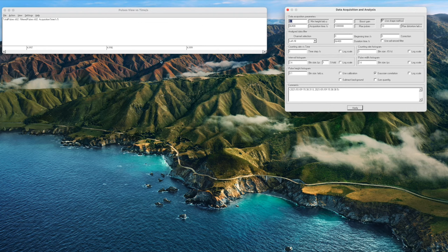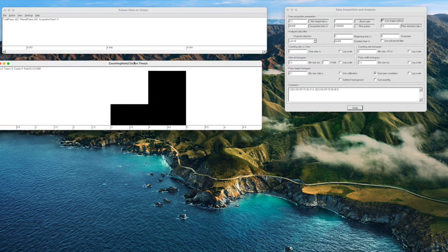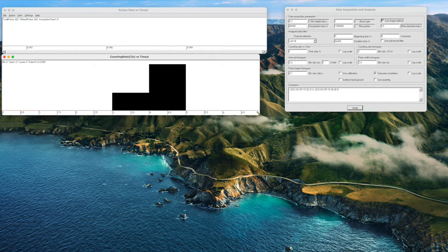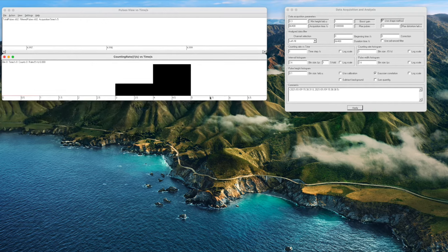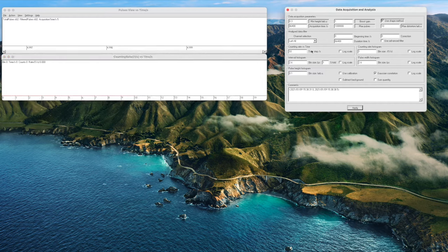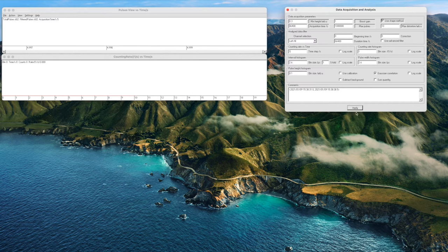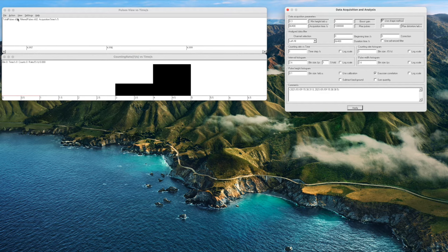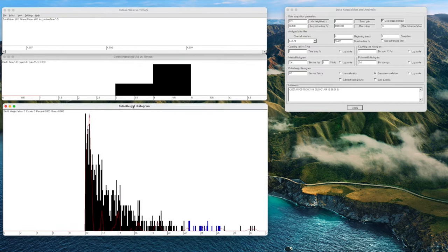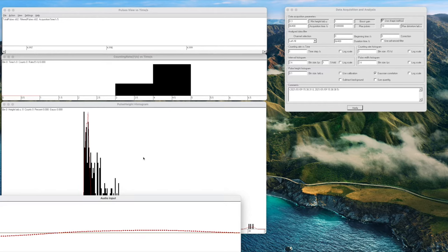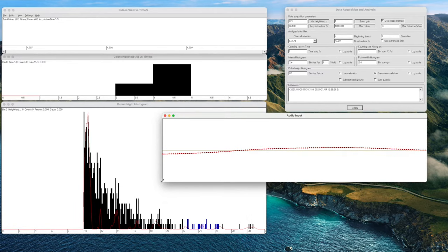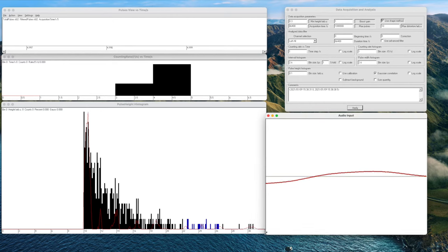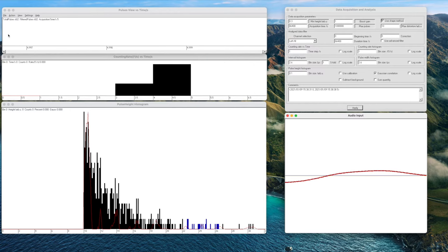The next window we are going to open is the count rate versus time. This window simply shows you how many counts per second by default but you can change the time interval here to every 10 seconds or 60 seconds or whichever time interval that you're interested in. We'll leave it at one second for the moment and click apply. The final window we're going to open here is pulse height histogram which is obviously your gamma spectrum that we're going to look at. And probably to see what's going on we also open the audio input window which gives us a graphical representation of the sound card input which is a bit like a poor man's oscilloscope.